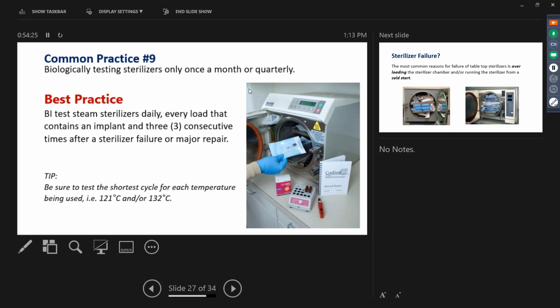Best practice says they're supposed to be testing their sterilizers daily, every load with an implant, and three consecutive times after sterilizer failure or major repair. So this is where the tabletop sterilizer repair company gets in. Since they're going to repair it off-site, they should actually do this test before they bring the sterilizer back. But guess what, they're not doing it, and they haven't told the office that they should do it, so it's not being done. So you're paying for repair, but they're not finalizing their QA. That should be part of what you're paying for.